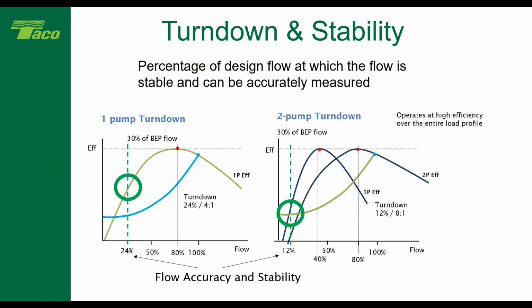What we have to understand is that in that scenario, as we start to slow down and come down to minimum load, if I've got duty standby pumps, I can only turn down so far. I can turn down to about 30% of BEP flow. So in essence, what that means is I've got about a 4-to-1 turn down out of that single pump.